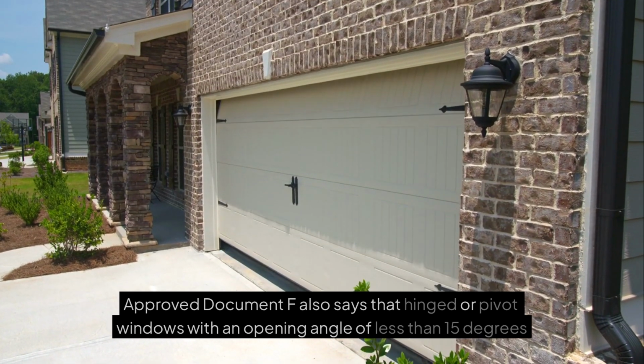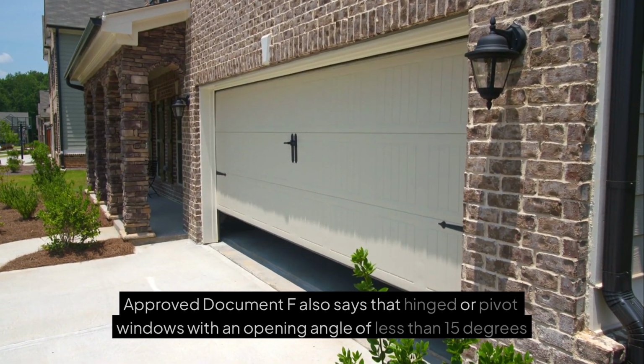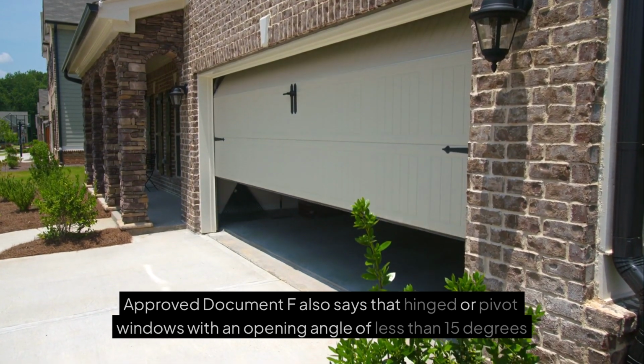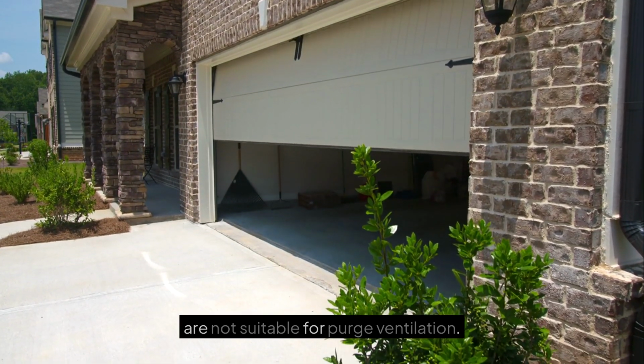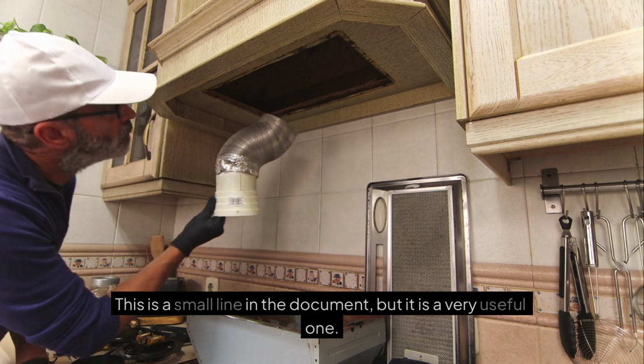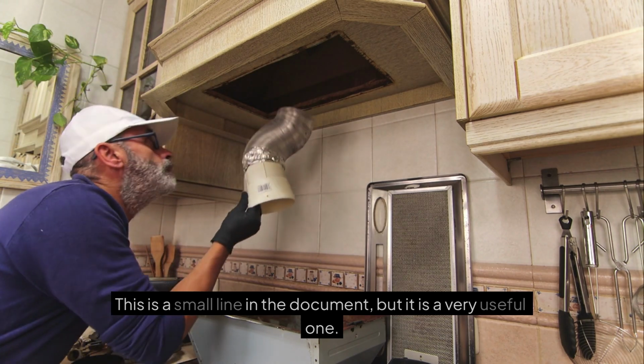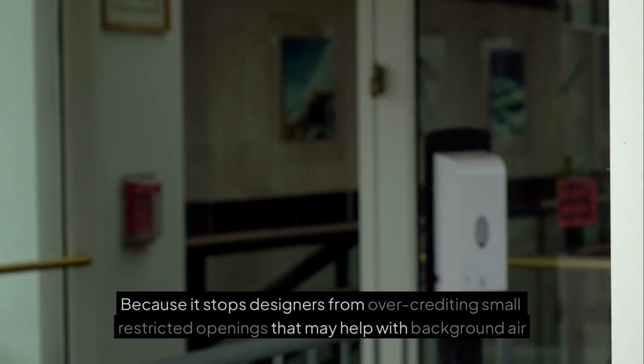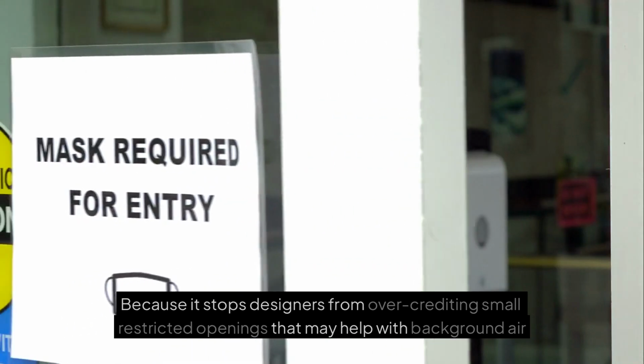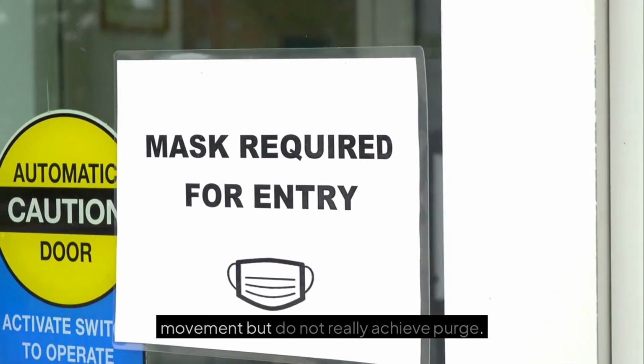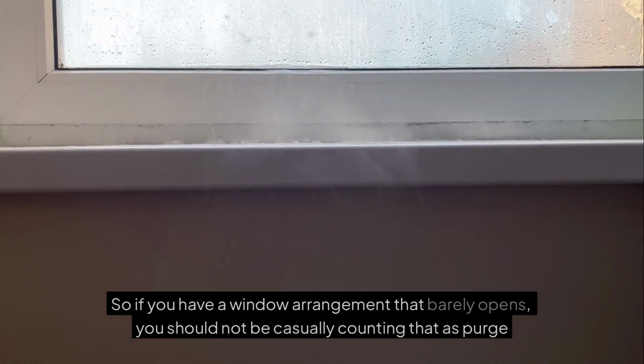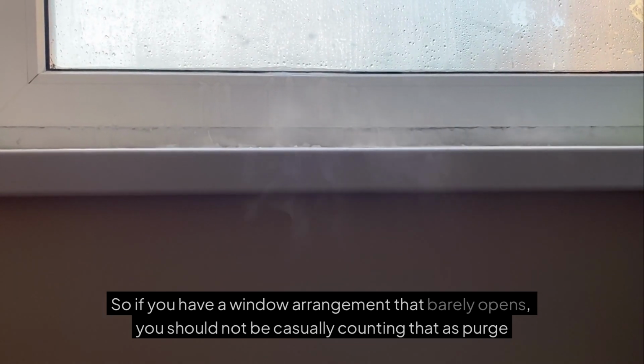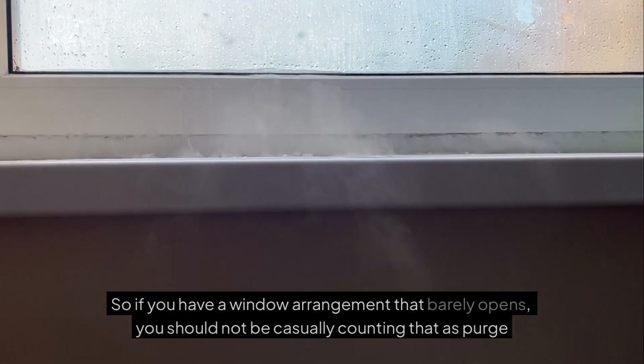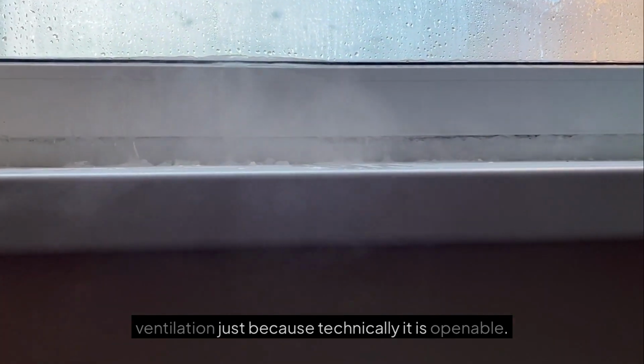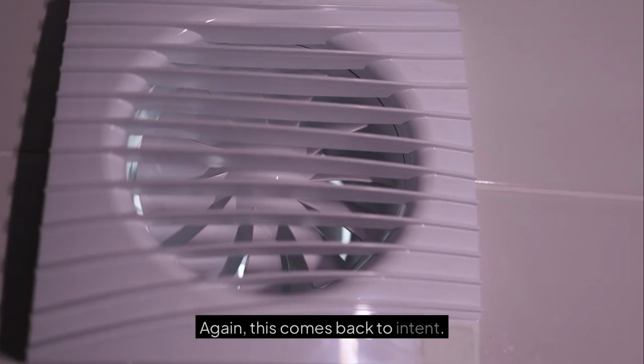Approved Document F also says that hinged or pivot windows with an opening angle of less than 15 degrees are not suitable for purge ventilation. This is a small line in the document, but it is a very useful one, because it stops designers from over-crediting small restricted openings that may help with background air movement but do not really achieve purge. So if you have a window arrangement that barely opens, you should not be casually counting that as purge ventilation just because technically it is openable.